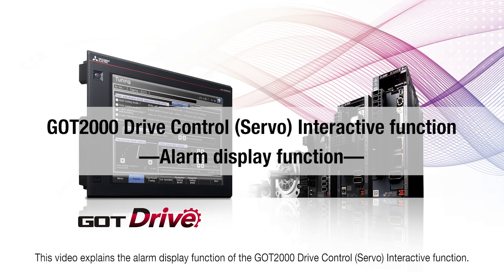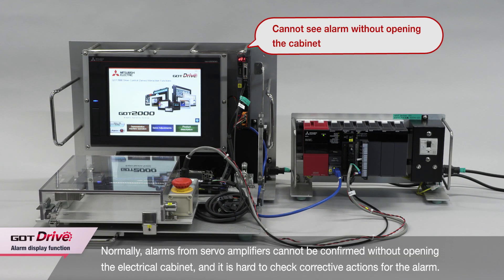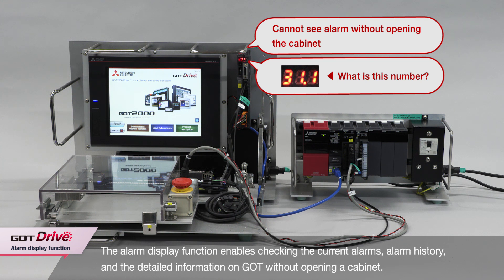We will introduce the Alarm Display function of the GOT2000 Drive Control Interactive function. Normally, alarms from servo amplifiers cannot be confirmed without opening the electrical cabinet, and it is hard to check corrective actions for the alarm. By using the Alarm Display function, you can confirm the current alarms and the detailed information on GOT without opening a cabinet.